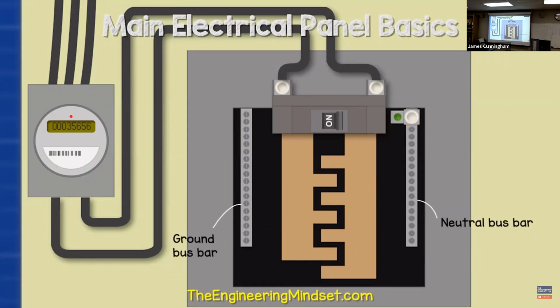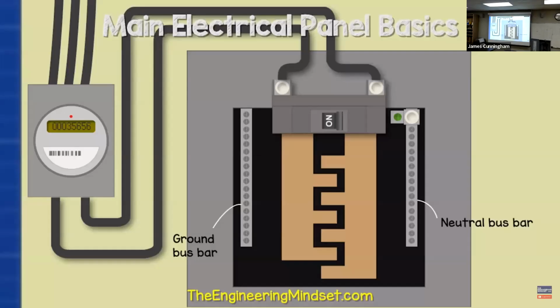Inside the panel, we also have a neutral and ground bus bar. This is basically a strip of metal with lots of holes and screws in it. The neutral and ground wires will sit in the holes and the screws will lock them in place. In this example, we have a block on either side of the panel. As this is a main panel, the 2 bus bars can be joined together.